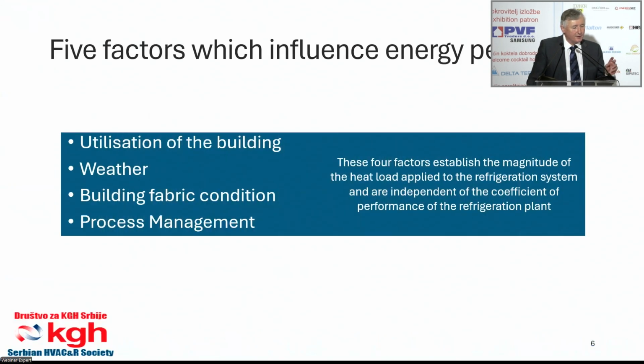So there are 4 factors that I grouped together here out of the 5 factors that I consider to influence the energy performance of a warehouse. And 4 of them: the utilization of the building, how busy is it; what the weather's doing; how good a condition is the building fabric, is the insulation in good shape or is it quite degraded; and how does the management run the building, how tight are they on the process. For example, do they permit product to come into the cold store much warmer than the store temperature, or do they actually manage that process and insist that goods are delivered at temperature beforehand?